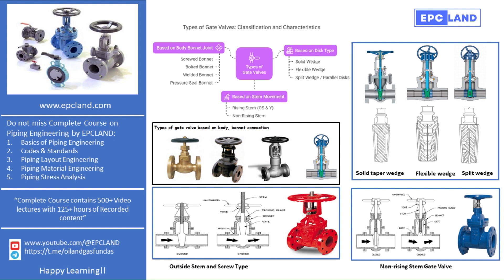Let's begin with the first classification: types of disc. Gate valves can have different types of disc or wedge inside them. The most common type is the solid taper wedge. This is the simplest and most widely used design. The solid wedge is strong and can be installed in any position. It works well with almost all types of fluids including turbulent flow. However, the solid wedge cannot adjust itself if the valve seat becomes slightly misaligned due to thermal expansion or external forces from the piping. This makes it more prone to leakage.